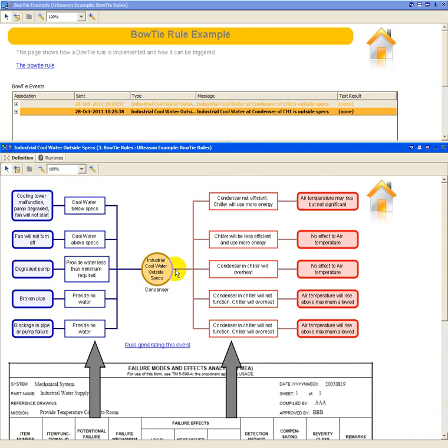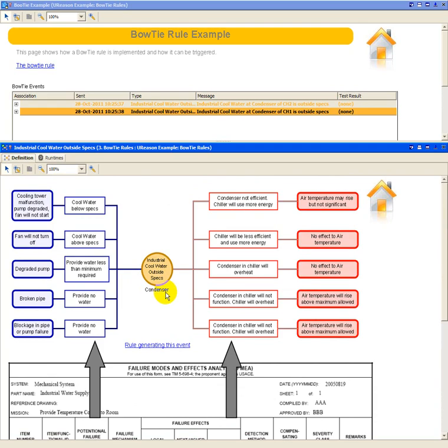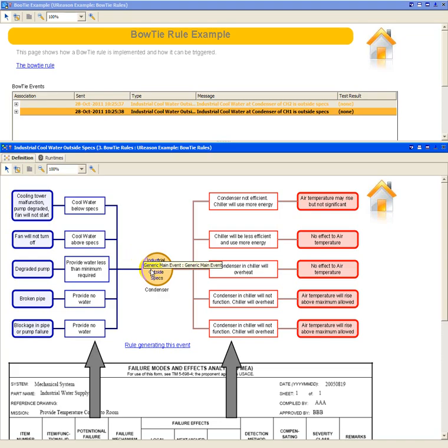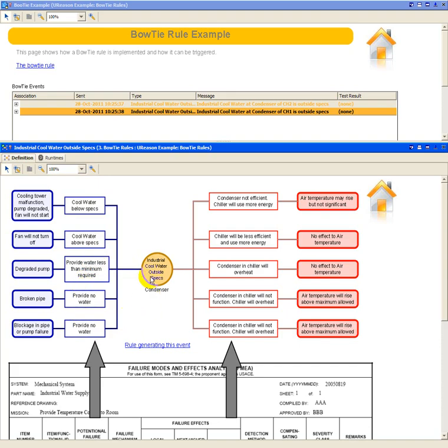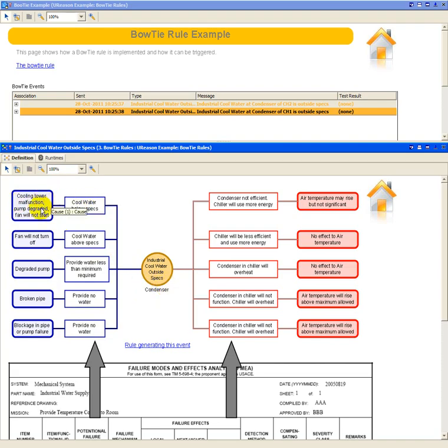So this rule, the central point of this rule is an event, an incident. In this case, the fact that the industrial cool water is outside a specification for a condenser. It's a generic rule. If that is the case, then the rule will be triggered and look at the possible causes for this outside spec event. And that is listed by all these blocks here.